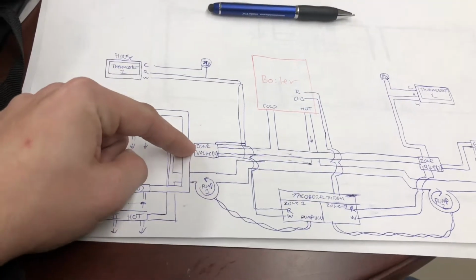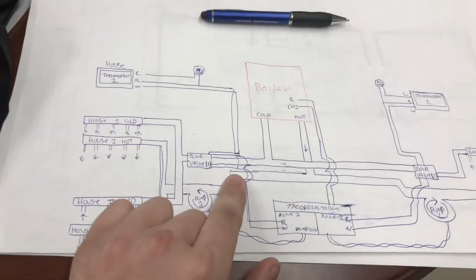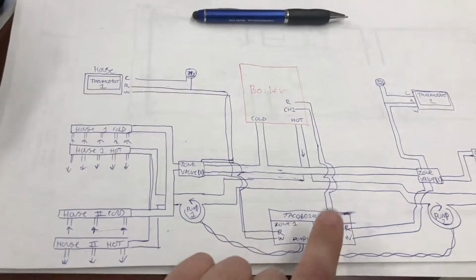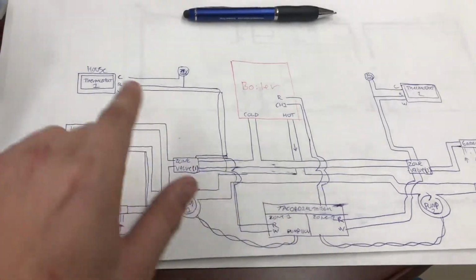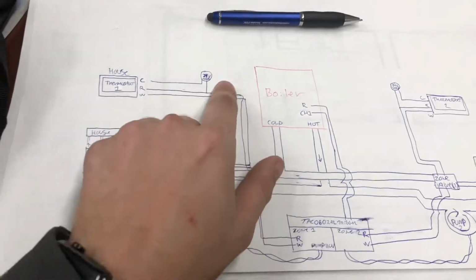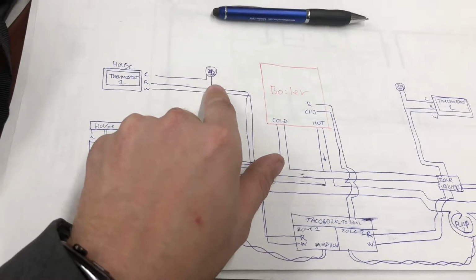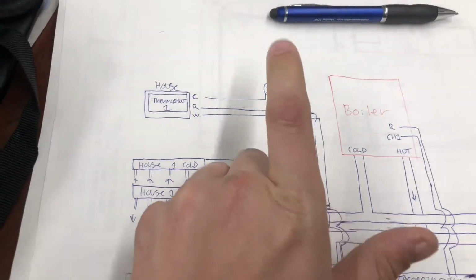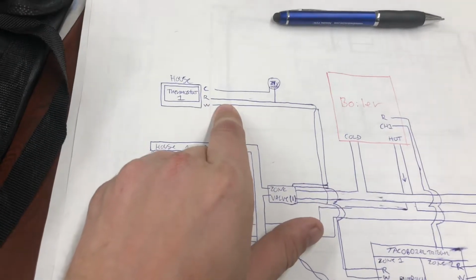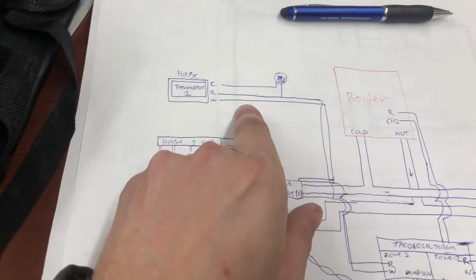Once it comes through the loop into the cold, then it comes into the zone valve, and then back to the cold, like that on the other side too. The only control aspect you need is your zone controller, which again, it starts with the thermostat. I would recommend supplemental 24 volt AC thermostat transformer just to power this. It just takes the load off the system. The only wires that are gonna come out of there are R and W.